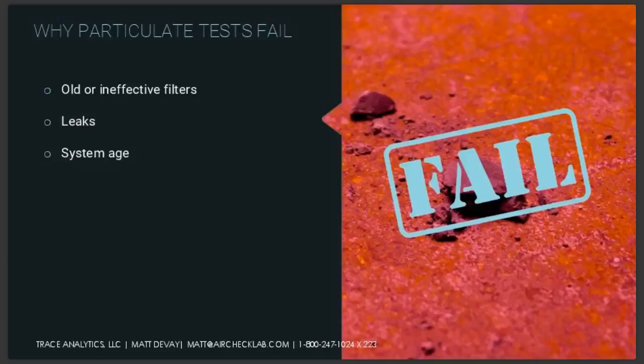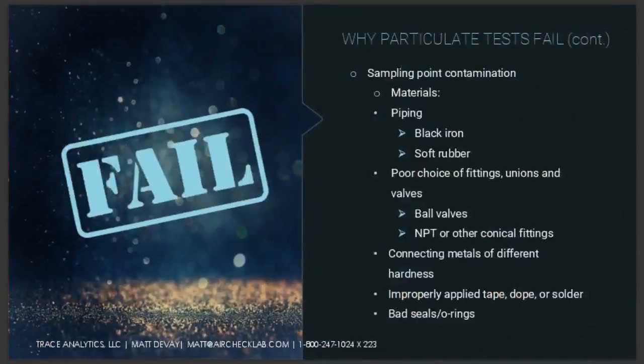Sampling point contamination. This can be environmental contamination, construction material contamination, things like black iron, soft rubber. These guys shed particles fairly well. Avoid them in your point of use. You definitely don't want to use these materials if you need to meet stricter particle classes. Poor choice of fittings, unions, and valves. So ball valves in particular are problematic. They have a lot of surface area. They have a lot of opportunity to collect contamination. Every time you turn that valve, you might be releasing some more of that into your system.